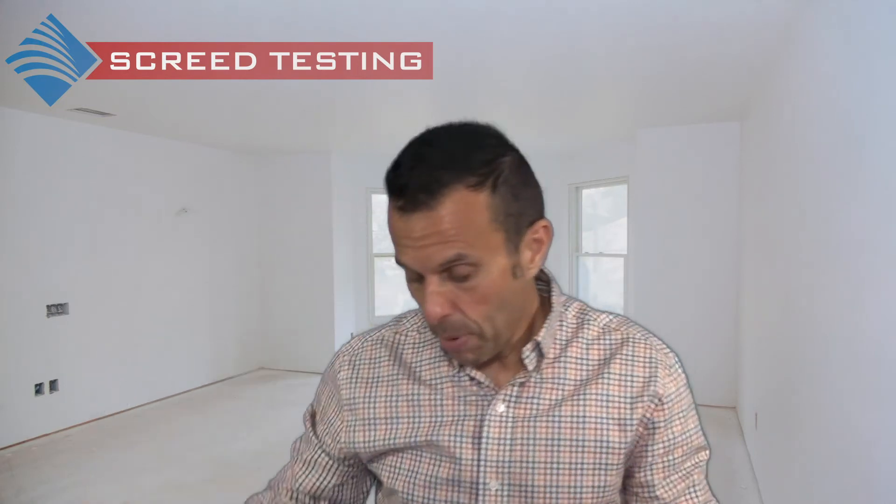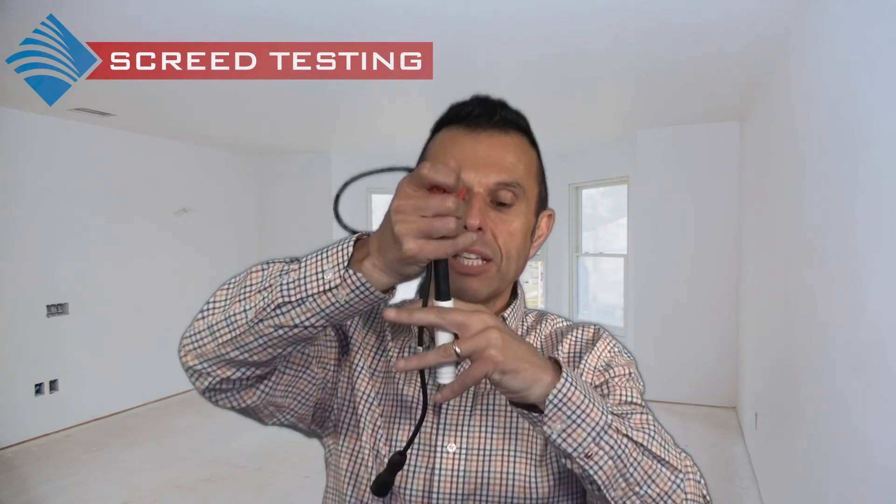Rather than using a box, the other method would be to actually insert a plug into the concrete or screed. Then, again after 72 hours or 24 hours, the probe is placed in and the relative humidity is measured. So relative humidity can be measured via the plug or the hygro-hood, and that will meet those British standards.